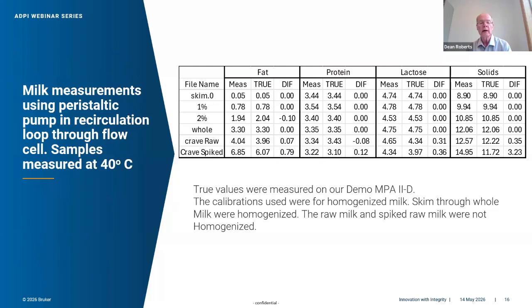We started off with the pasteurized homogenized milk, and then I got some milk from one of our customers locally here that has a higher butterfat content. And then I spiked that with cream to really pump it up there. Now, in some of the existing technologies we've been using for analysis of raw milk, after you get to about 3.5% butterfat concentration in the milk, you're pretty much done because the fat droplets scatter the beam so severely that you just run out of signal. And I wanted to see if I could take this flow cell to a higher level of butterfat content.